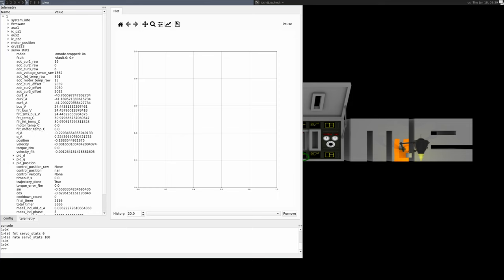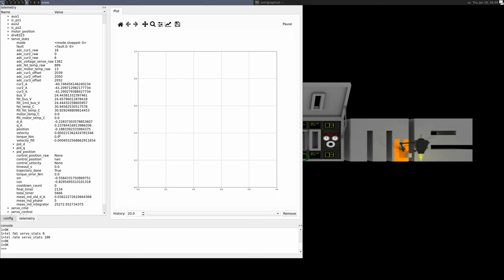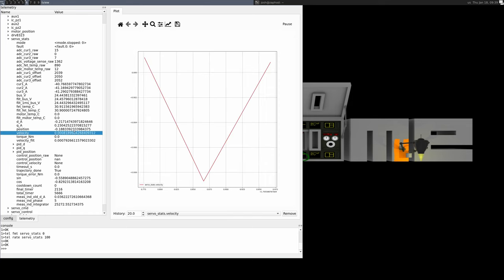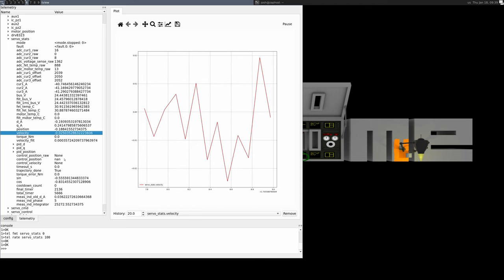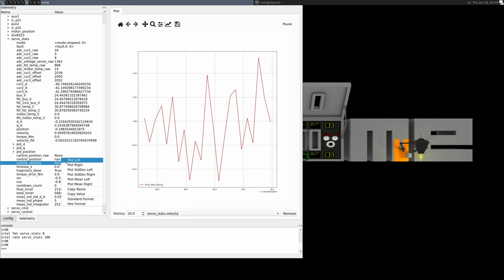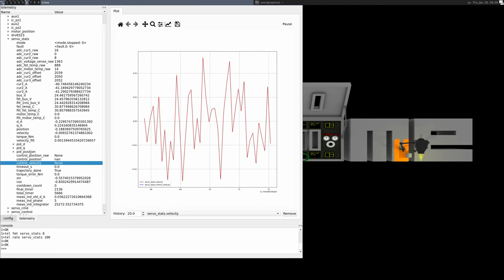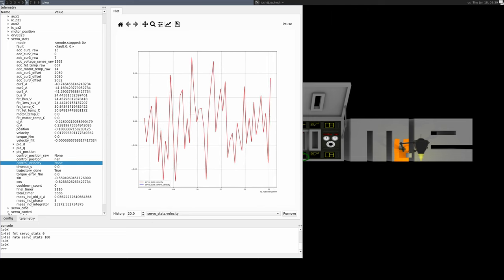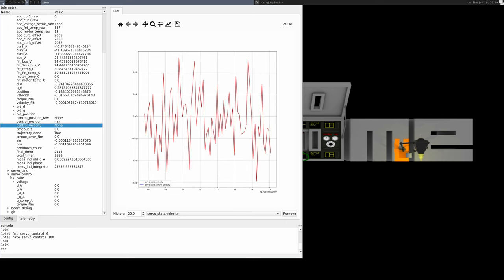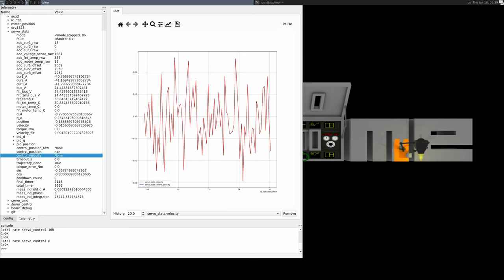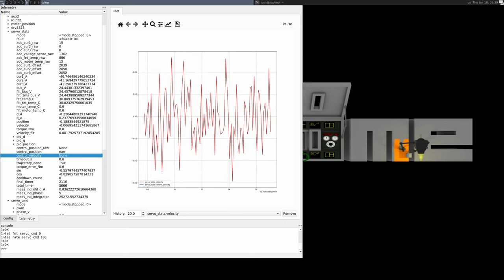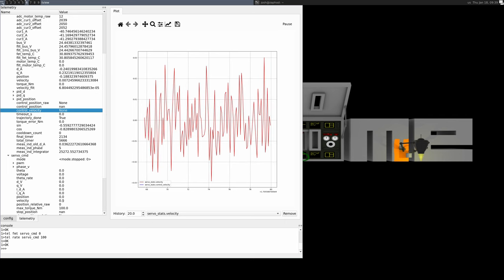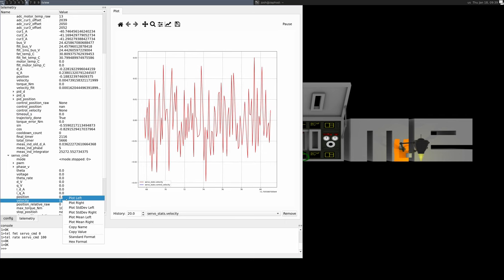Next, I'll plot some values. The measured velocity is estimated from the primary position sensor. The control velocity is the internally interpolated velocity that obeys any in-effect acceleration or velocity limits. And the command velocity is the value we are commanding, which will change instantaneously as new commands are sent.